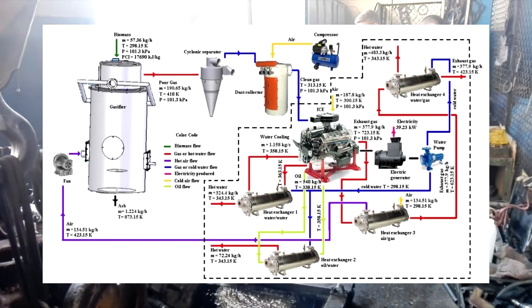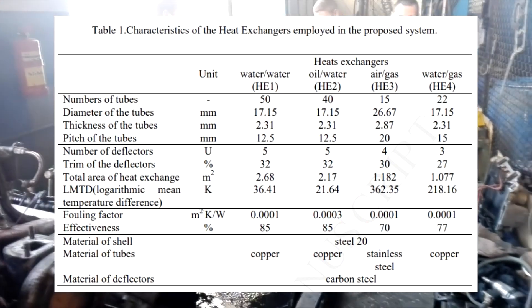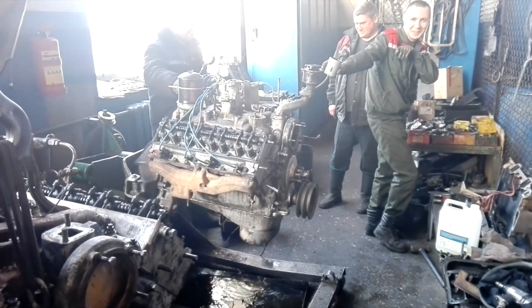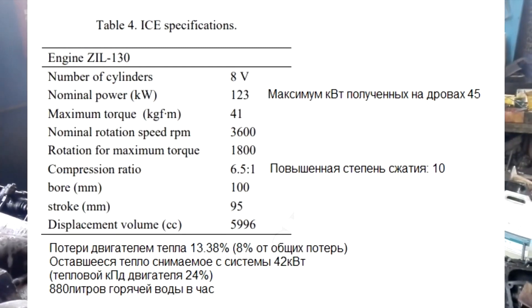Some of the heat produced by the co-generator is dissipated naturally — its share is 13.38 percent of generated heat, or 8 percent of total heat. The system produces 880 liters of hot water per hour from three heat exchangers. Maximum efficiency was 24 percent for electricity and 32 percent for heat; electric generator efficiency was 95 percent. As we can see, the declared engine characteristics of 123 kilowatts reduced to only 45 kilowatts of electricity when converted to firewood — 2.73 times less. To calculate real engine power on firewood, divide the declared power by 2.73 at a compression ratio of 10.